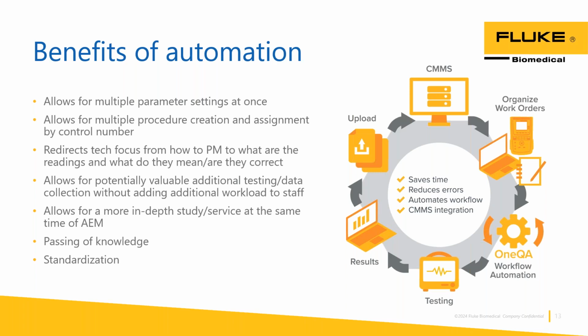Now, the next thing I want to point out is when we're talking about automating patient monitor testing, we're automating a simulator. So some of the things people notice is, well, hey, listen, when I'm automating my simulation, I still have to type my results back into the PC. That's right. So Fluke sells two things. We sell analyzers and we sell simulators. With an analyzer, we're going to look at a medical device's output and we're going to record it and see what that output is, like a defibrillator or an ESU.